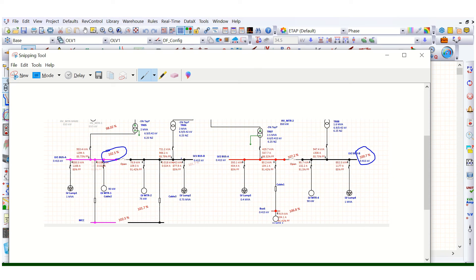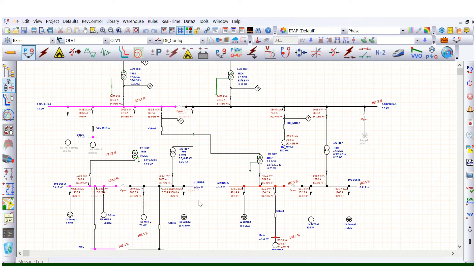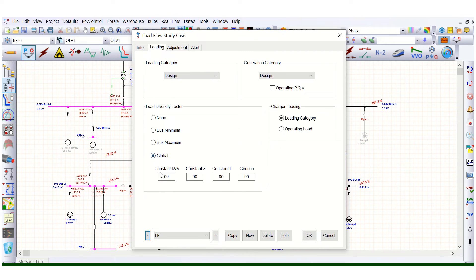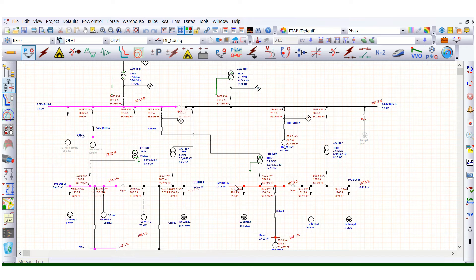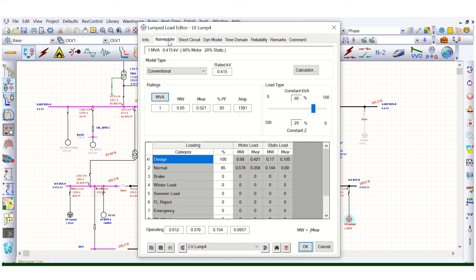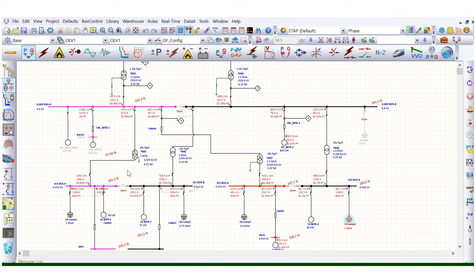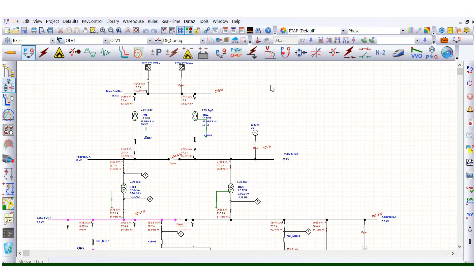The result is 102.3 percent. Previously with normal loading it was 102.5 percent, so there is a slight difference. This is because we applied the load diversity factor of 90 percent globally at all loads and all buses. However, for the lump load we had defined 85 percent, but now we are applying 90 percent on top of the 100 percent design load — that's why this slight difference is coming. This is acceptable. This brings us to when we actually need to apply the load diversity factor or global diversity factor.